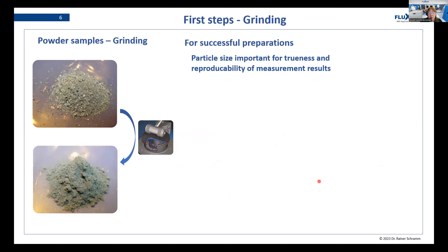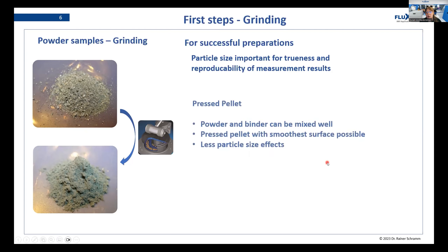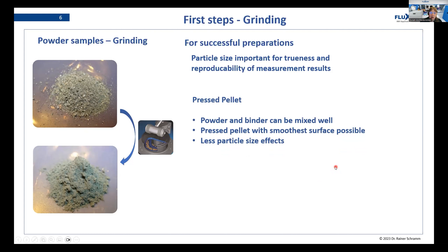First, we need to make sure that the particle size of our sample is fine enough to do either of the preparations. Grinding is a very important step for successful preparation. The particle size is very important because it will affect the trueness and also the reproducibility of your measurement results. For pressed pellets, it has some advantages to grind the slag to become a very fine powder.